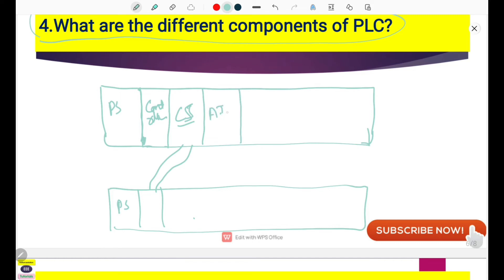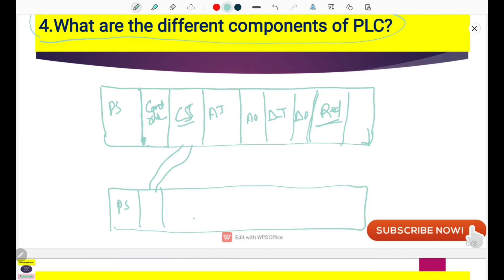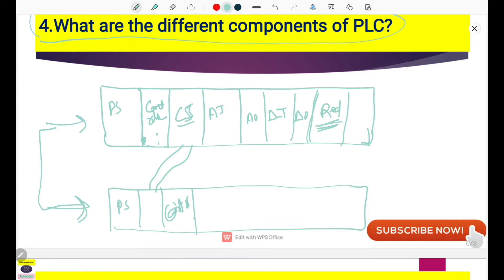The communication card communicates to your controller to keep it up to date. Then you have your I/O cards: analog input card, analog output card, digital input card, and digital output card. These are the components of the PLC. Sometimes a redundancy card is also available. Redundancy is used when you want to make a redundant pair of racks — a second rack has another controller installed, and the redundancy card maintains the redundancy. When this chassis controller fails, the redundancy module transfers total control to the other chassis.